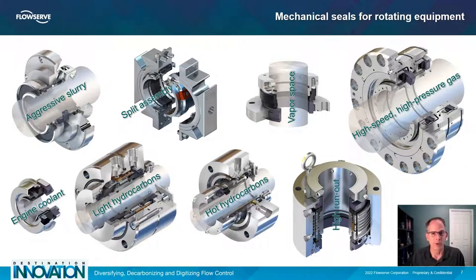Considering the variety of rotating equipment and range of application conditions, there's not just one mechanical seal that serves all purposes. A seal designed for aggressive slurry services where abrasion and erosion attack the seal elements is different than one for light hydrocarbons where vapor pressure margin and flashing are the primary concern. A low-duty water pump seal with elastomer gaskets would be out of place in a high-temperature hydrocarbon service or molten salt where elastomer gaskets melt. Mixing equipment typically has higher runout, so the seal must tolerate such movement. Top entry mixers need vapor sealing, bottom entry mixers have the seal fully immersed in liquid that might turn into powder, and side entry mixers could see a combination of everything.